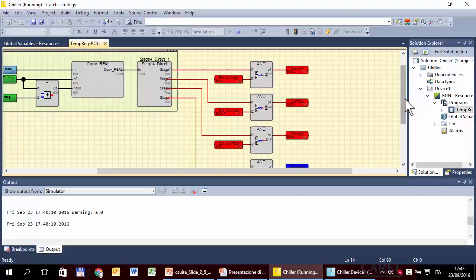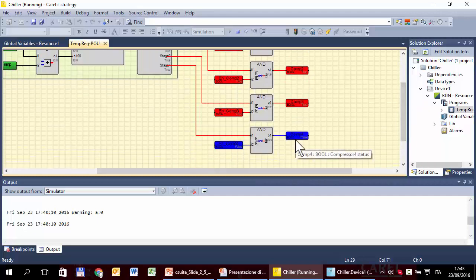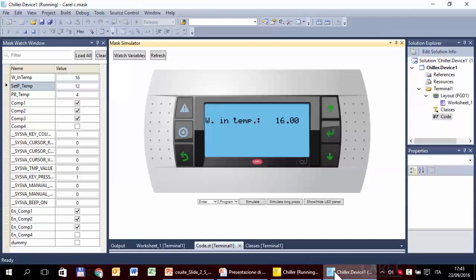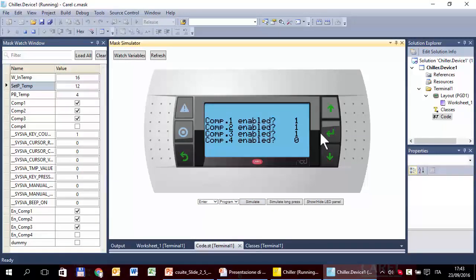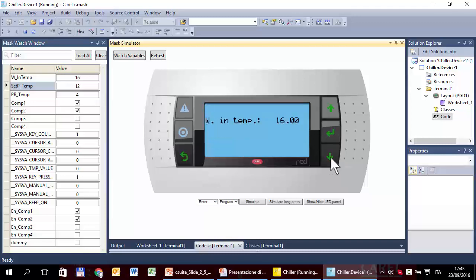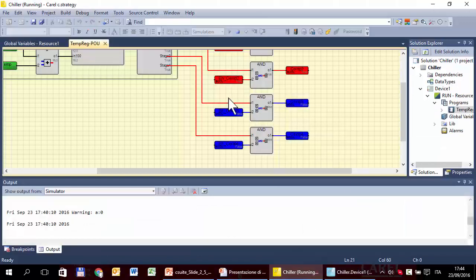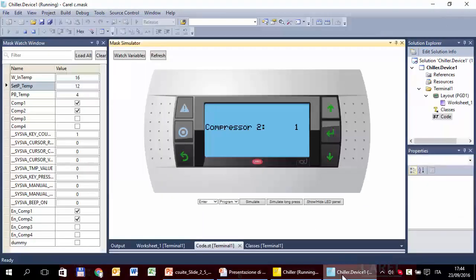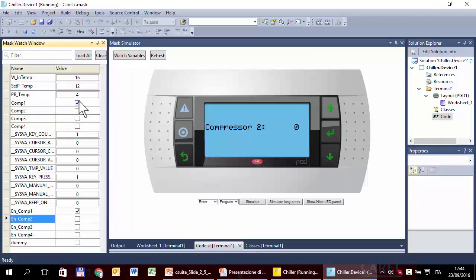We can check this also in the strategy. Then continue with other tests — we can disable compressor three. We should see only one and two. In fact, one and two. Compressor three is forced off — we can see this here and also here. We can also disable compressor two from here. The compressor two has been switched off, forced off.